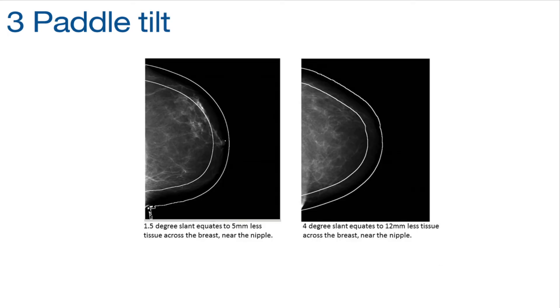Paddle tilt is also reported in Volpara Analytics. In another case, it identified a unit with a tilting paddle that reported 30% more pressure than other units, resulting in a 4-degree tilt angle while others were 2 degrees. By standardising the pressure, patient experience and image quality variability were reduced.